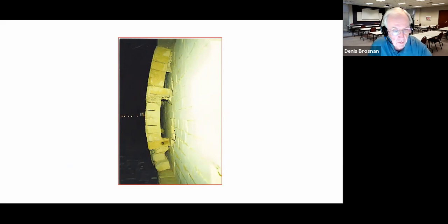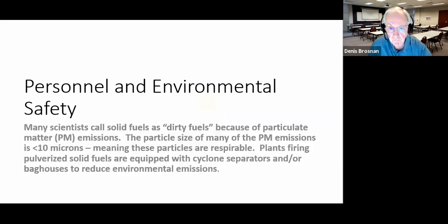So I have also investigated coal effects on refractories. They're not nearly as severe as the potassium in the wood ash and petroleum coke effect on refractories. And I did this in some detail with petroleum coke and could find no adverse effect in the short term.